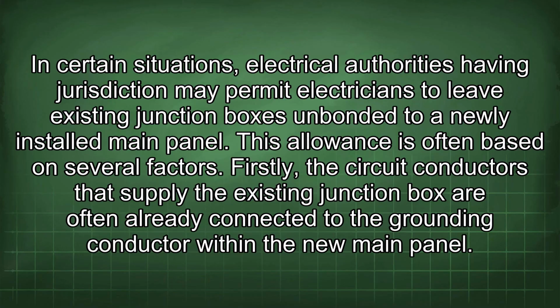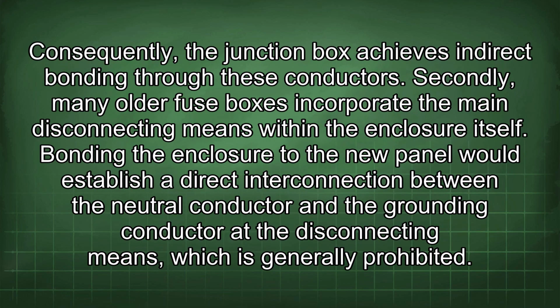In certain situations, electrical authorities having jurisdiction may permit electricians to leave existing junction boxes unbonded to a newly installed main panel. This allowance is often based on several factors. Firstly, the circuit conductors that supply the existing junction box are often already connected to the grounding conductor within the new main panel. Consequently, the junction box achieves indirect bonding through these conductors.